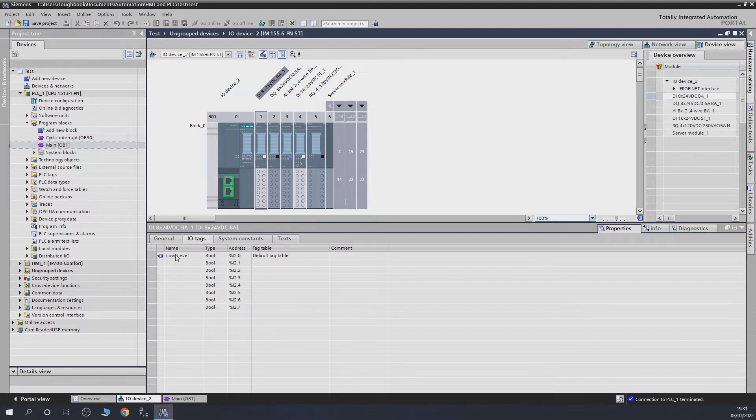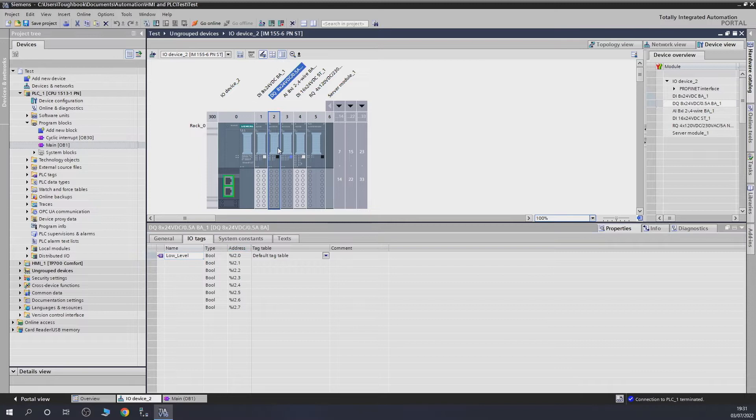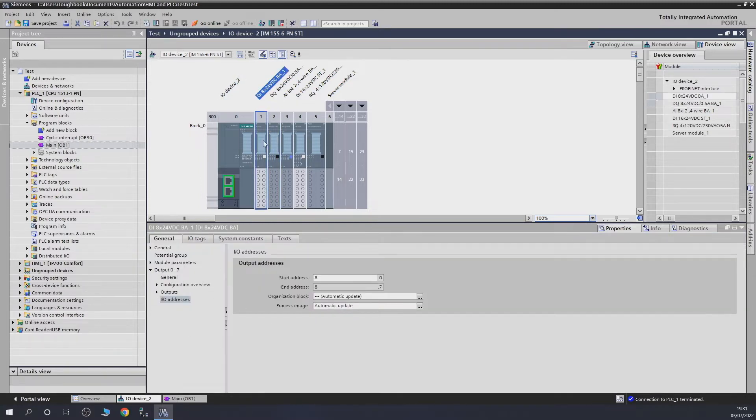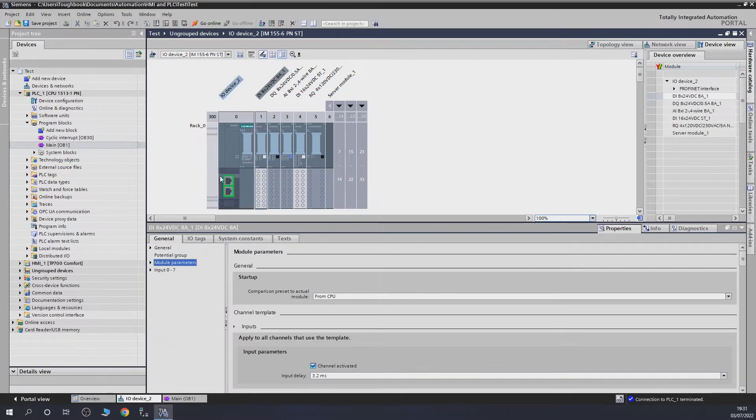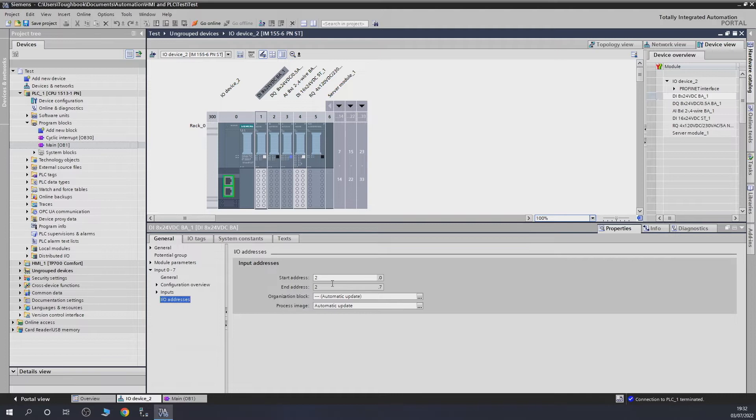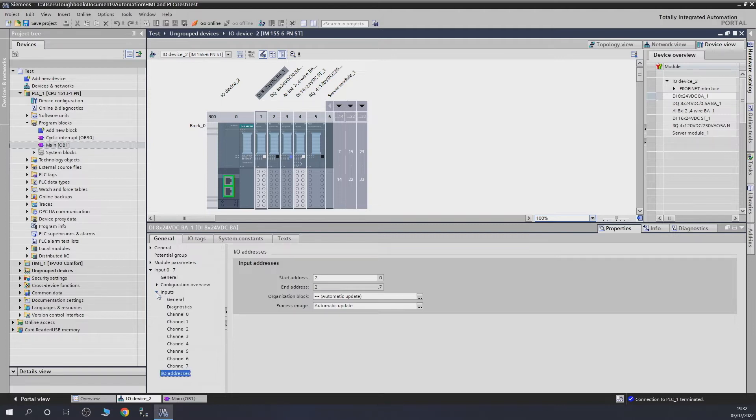As you can see, this card has been assigned 2.0 all the way to 2.7. Remember, we have wired in our black wire into 2.0, and in our terminals, that's going to be our first terminal on our base unit, and that is going to be 2.0. Same applies to output. By the way, if you don't want it to be 2.0, you can change the addressing here if you wish to. But usually, I don't think you need to. The TIA Portal assigns these things appropriately to what's available, so make sure they don't clash.